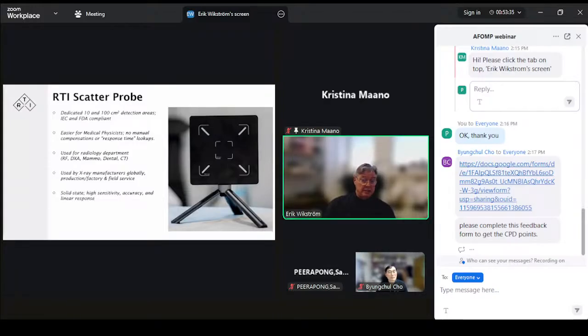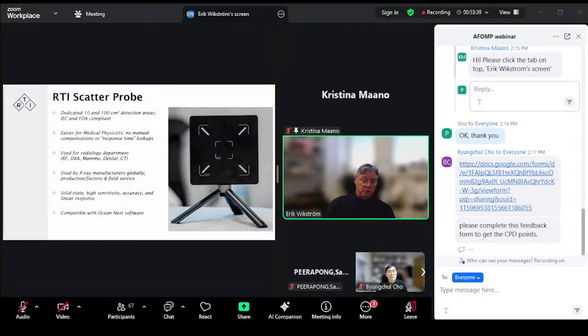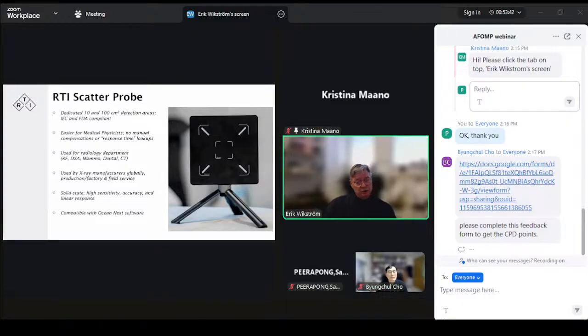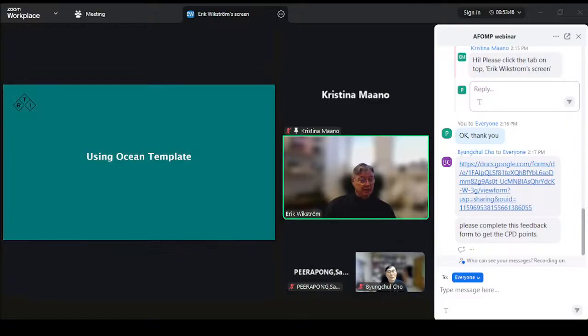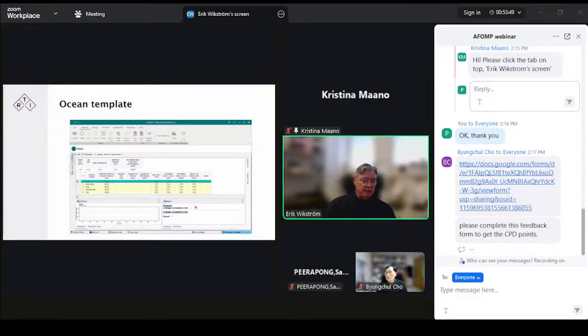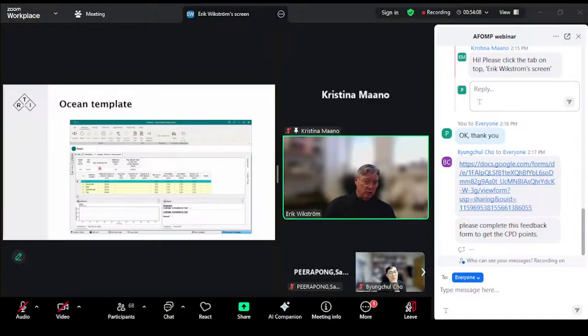Like I said, it's solid state, has a high sensitivity and good accuracy, and it's compatible with the Ocean software. You saw the display there, which is the simple one. There is also the possibility of using templates in the Ocean. Here's one example of a template set up to measure the leakage from a tube in 5 different areas: front, anode, rear, cathode, and top. We feed it with the settings that we've made. Maximum continuous mA gives us how many exposures like this can be done in 1 hour.